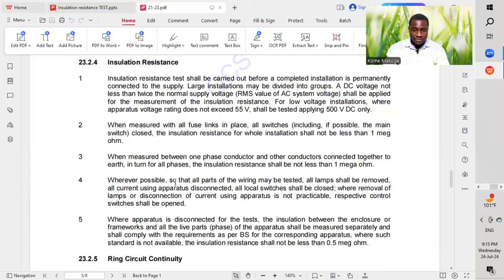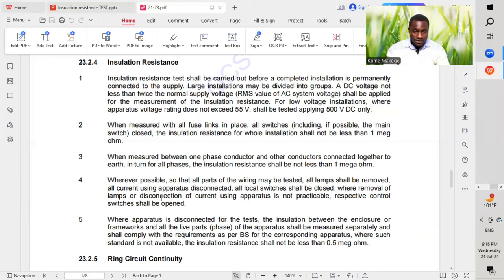The fourth point: wherever possible, so that all parts of the wiring may be tested, all lamps shall be removed, all current-using apparatus disconnected, and all local switches shall be closed. Where removal of lamps or disconnection of current-using apparatus is not practicable, the respective control switches shall be opened.